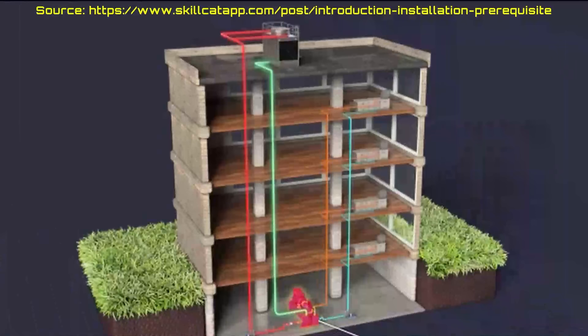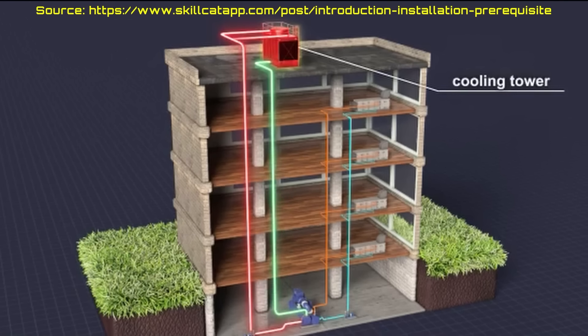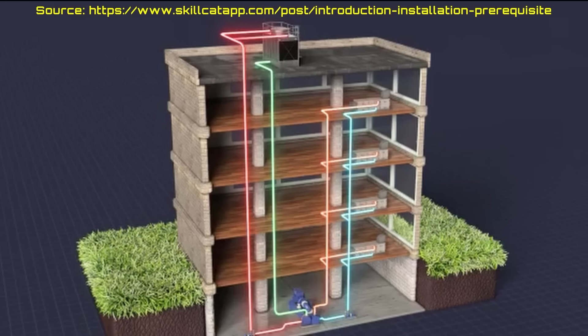Water-cooled chillers release thermal energy from the refrigerant in the condenser to a cooling water loop, which is then pumped to a cooling tower where it is cooled for reuse. Water-cooled chillers are more costly to install, but they are more efficient and are often used in larger commercial properties with higher cooling loads. Chiller systems have one or two extra water loops involved with the heat transfer process, because the refrigerant receives thermal energy from liquid water instead of air, and a different type of heat exchanger is required.